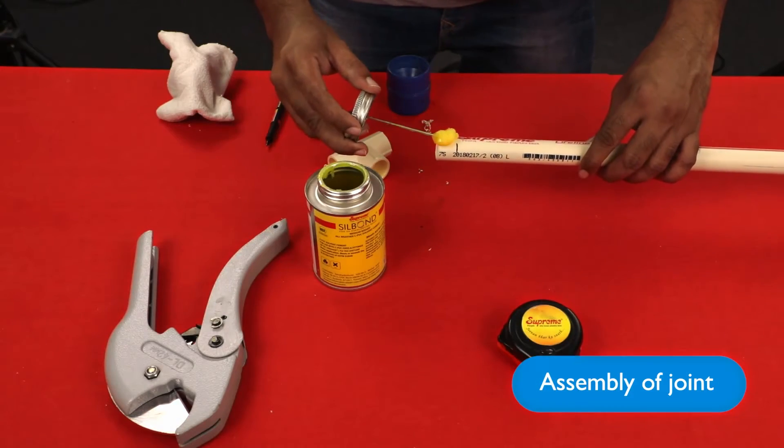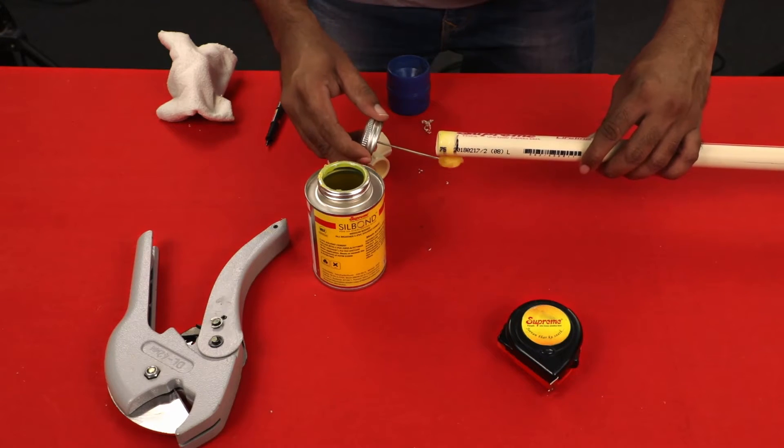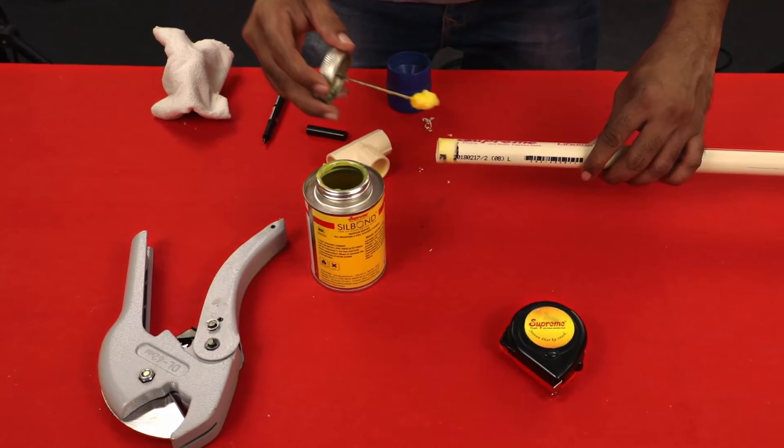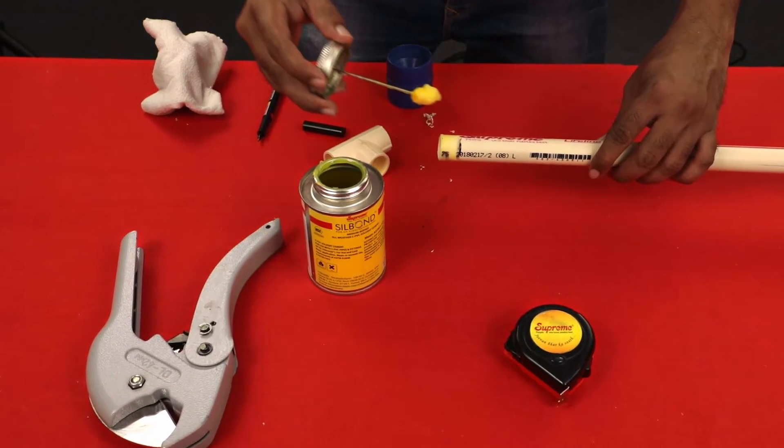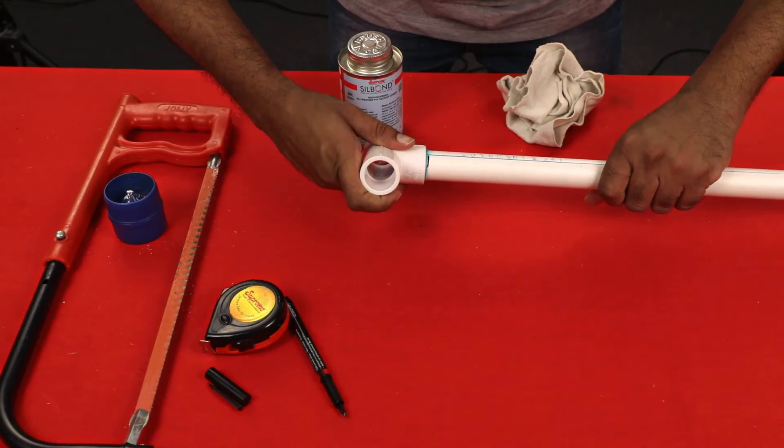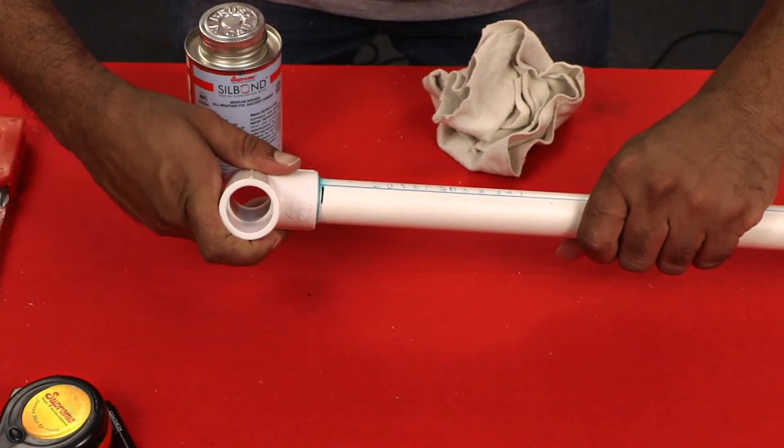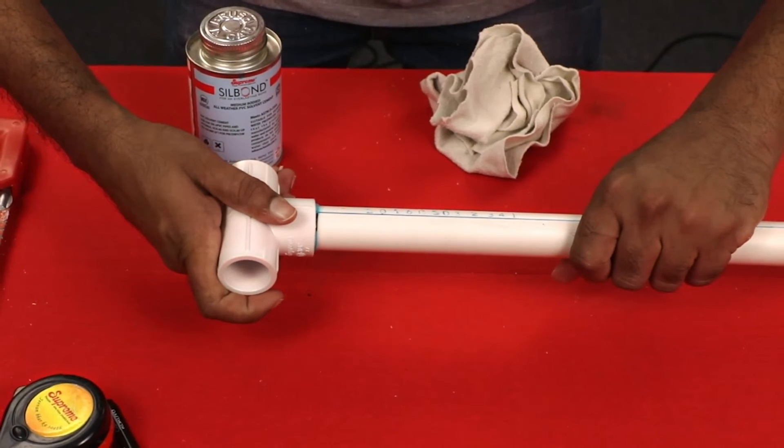Assembly of Joint: Immediately after applying the last coat of cement to the pipe and while the cement is still not dry, that is within 10 to 20 seconds, forcefully bottom the male end of the pipe in the socket, giving pipe or fitting one-fourth turn to distribute cement evenly.